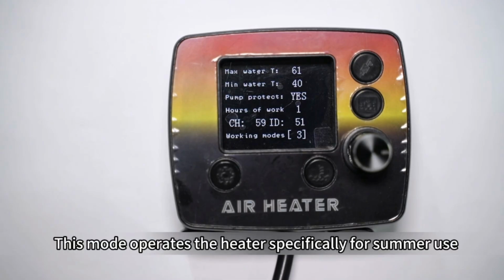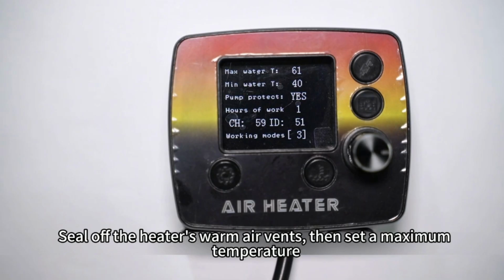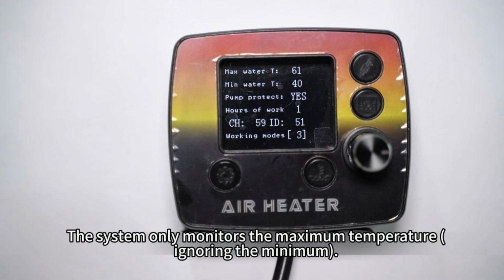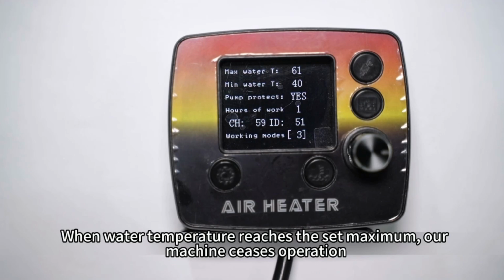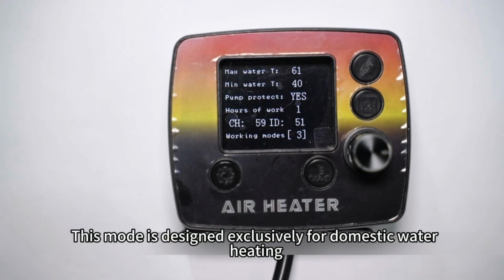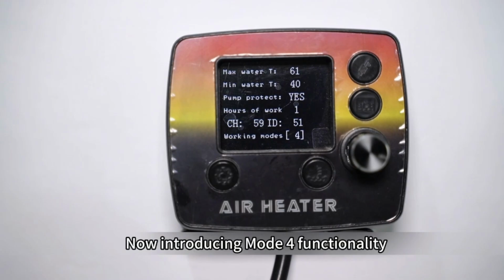This mode operates the heater specifically for summer use. Seal off the heater's warm air vents, then set a maximum temperature. The system only monitors the maximum temperature, ignoring the minimum. When water temperature reaches the set maximum, our machine ceases operation. This mode is designed exclusively for domestic water heating. Now introducing Mode 4 functionality.